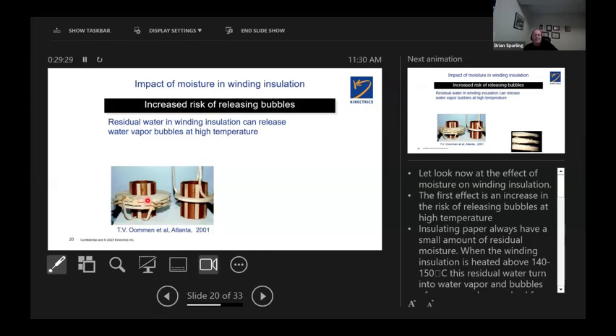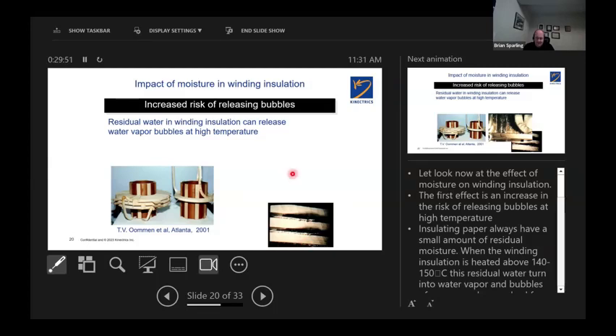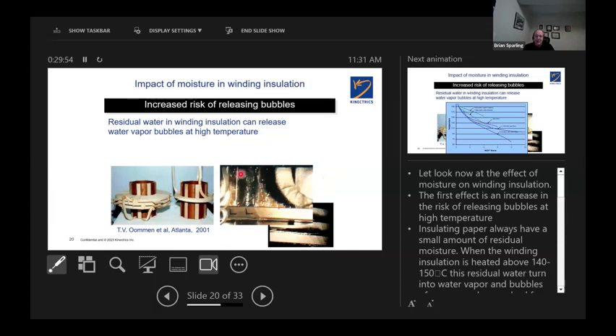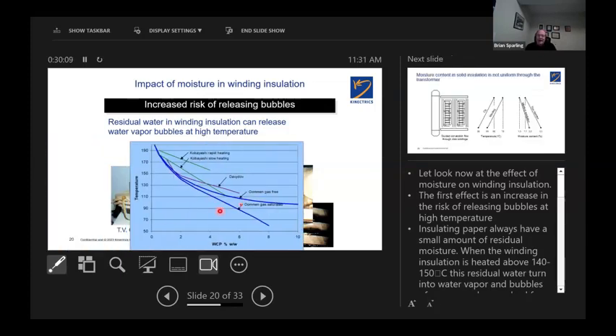So he began to doctor or make the oil wetter and wetter, and therefore make the paper wetter and wetter. And this is where he was able to demonstrate using this that he could induce the moisture coming out of the paper in the form of steam, water vapor bubbles. That's steam. It's on top, and you can see water vapor bubbles underneath. And off this one here, now this, you can see the water vapor bubbles streaming up somewhere into the upper part of the transformer. And these are, again, water vapor bubbles. This is not combustible gas bubbles. Don't get confused on that. This is steam. And this is how they came up with this.